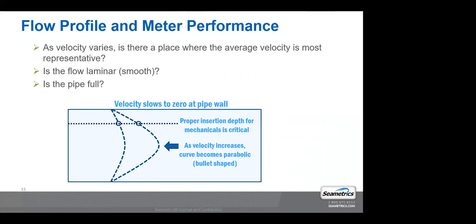On mechanical meters, there's typically no leeway there. You've got to have that straight run to get some of that swirl out. If your flow comes through an elbow and it's swirling, it's got to be straightened out. So you can use flow straighteners, wafer cones, whatever that meter manufacturer has to help take the swirl out of the water. But it's critical you follow those instructions or you're not going to have an accurate meter. You might get a reading on it. That dial might be moving around and spinning, but it's not going to be an accurate reading.